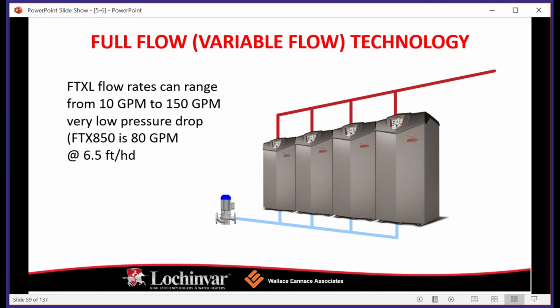This goes back to a water tube versus a fire tube design. Okay, so a fire tube boiler is going to allow you to install your boiler in a full flow or variable flow. Variable meaning we're varying the speed of the water as it travels through the heat exchangers to the building, or you can do what's called primary secondary, which is much more common. For a water tube boiler, we're going to require primary secondary.